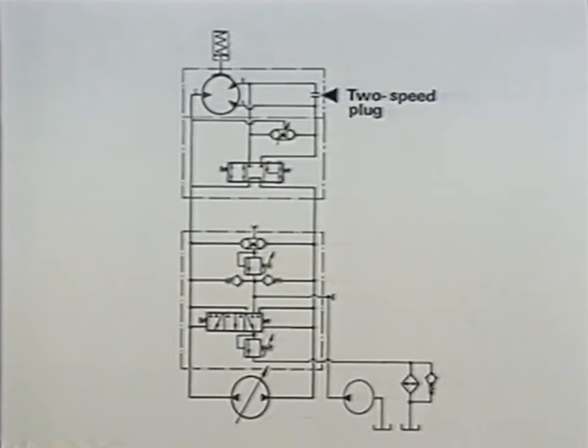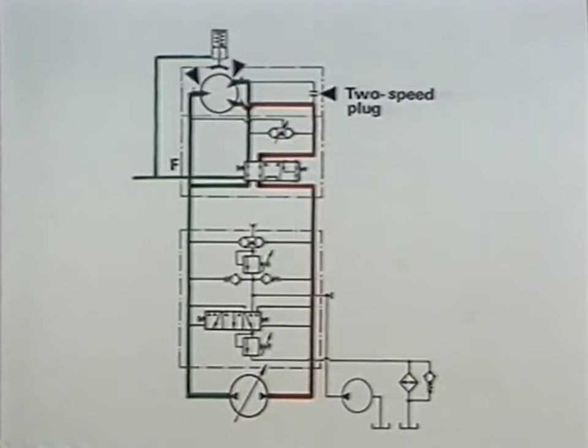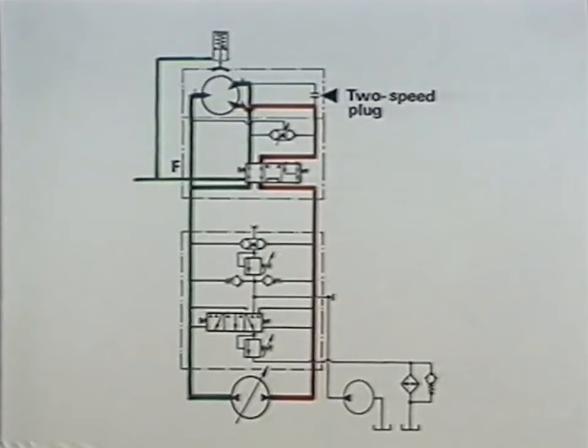By applying pilot pressure at the F connection, the two-speed valve spool is shifted to a position where hydraulic motor ports B and C are connected to each other.